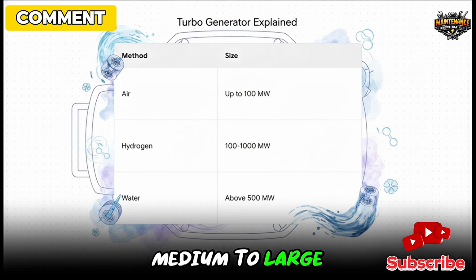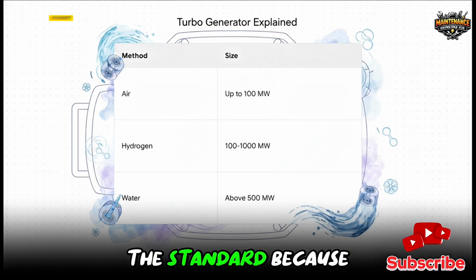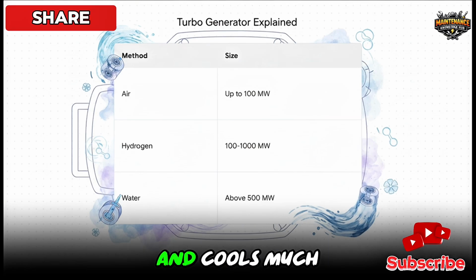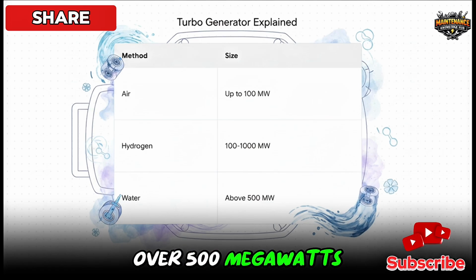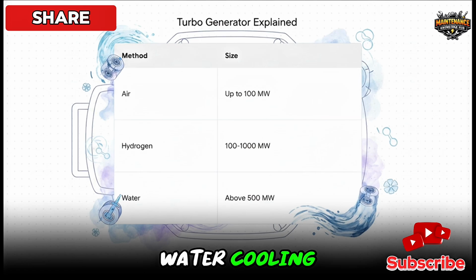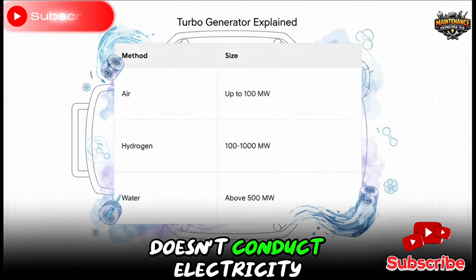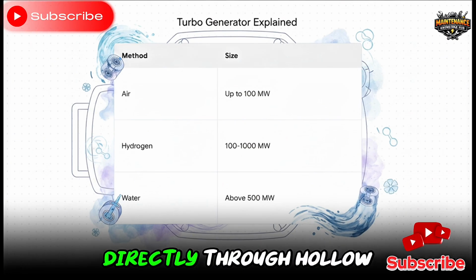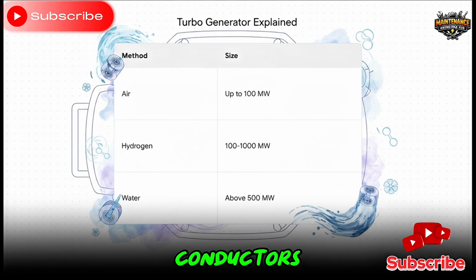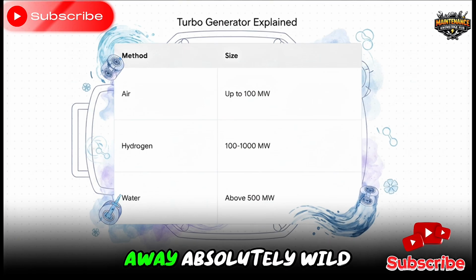For medium to large generators, between 100 and 1,000 megawatts, hydrogen cooling is the standard, because it creates far less friction and cools much better than air. But for the true giants, generators over 500 megawatts, they actually use water cooling. Think about that for a second. It's an incredible engineering feat, where pure, demineralized water, which doesn't conduct electricity, is literally pumped directly through hollow high-voltage stator conductors to rip massive amounts of heat away.